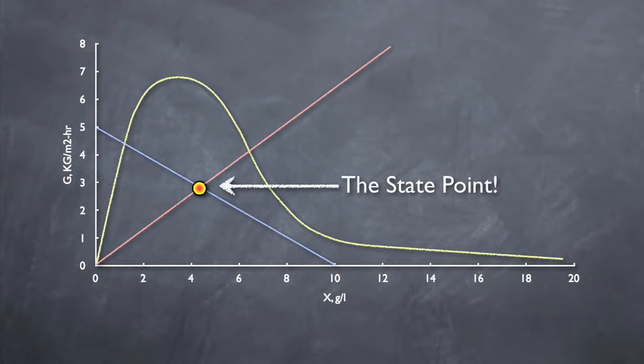However, getting the state point under the curve isn't the only goal. In order to ensure proper thickening of the sludge, we want to make sure that the entire underflow rate line to the right of the state point falls under the settling curve as well.